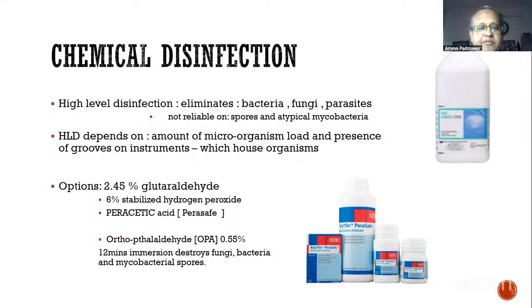It is ineffective. Even if you have used it only once, still it has a shelf life of only 14 days on activation. Okay. After that, you cannot use it, and you have to make a new set of solution for the subsequent case. The high level disinfection, again, when you reuse the same solution again and again for subsequent cases, depending on the microorganism load and the presence of residual proteinaceous material, if the solution gets cloudy, you cannot see the bottom of the container through it very well, then you have to change the solution.